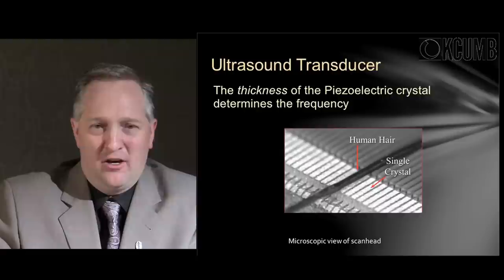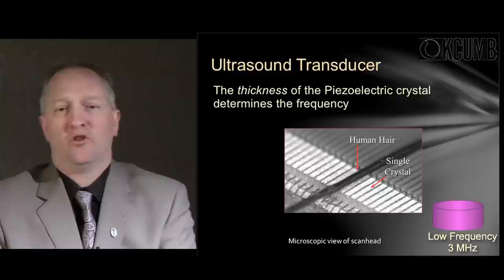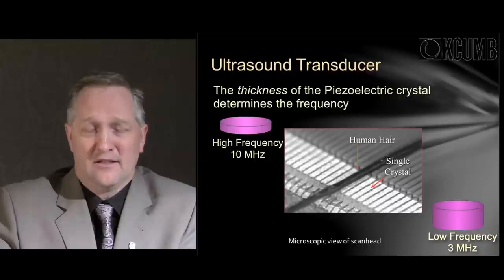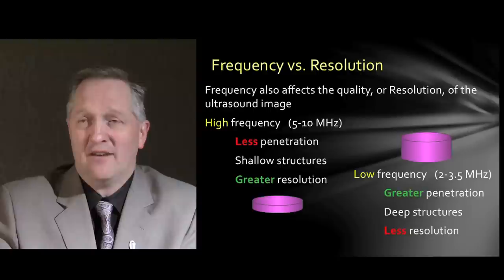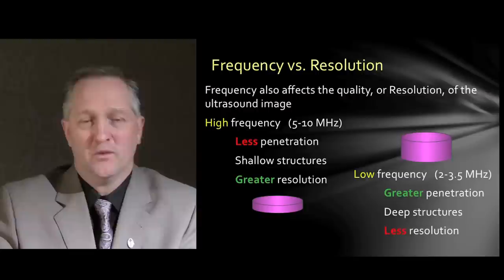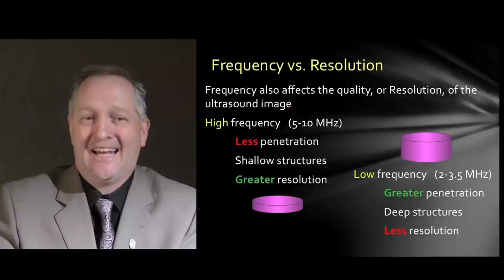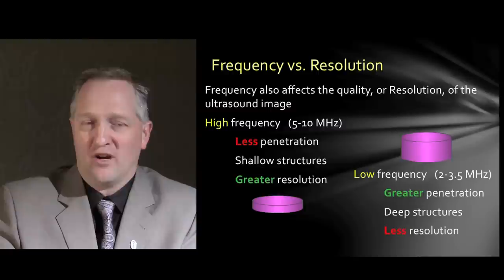The crystals in the probe are extremely small — as thick as or thinner than a human hair. For low frequency, the crystal is physically thicker and produces roughly a 3 megahertz vibration. High frequency uses a thinner crystal that can vibrate at a higher rate, up to 10 megahertz. The size of the crystal directly determines the frequency and the resolution you achieve. A smaller, high-frequency crystal vibrates faster, producing more cycles per second, but the problem is it penetrates less — you can only image shallow structures.